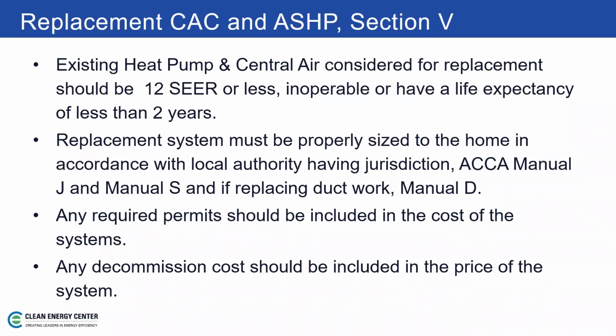So are we repairing them if they are below 15 SEER rating? I think you have an opportunity to replace them at that point based on Section 5. 12 SEER was probably, I'm going to say, late 80s. So you're well beyond the life expectancy of that unit probably. Maybe there again, say 13, 14 SEER now. Do you want us repairing the 13, 14 SEERs? Or are we back at that criteria where, okay, we're not at 15, so now we're not repairing them? I think you've got to use some judgment there. There is the last section that says or have a life expectancy of less than 2 years.